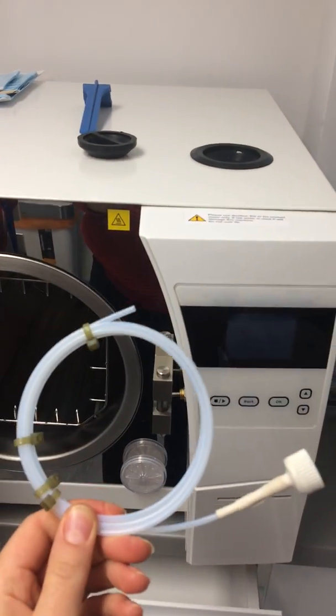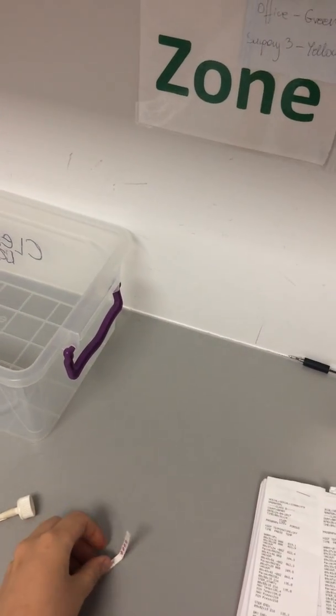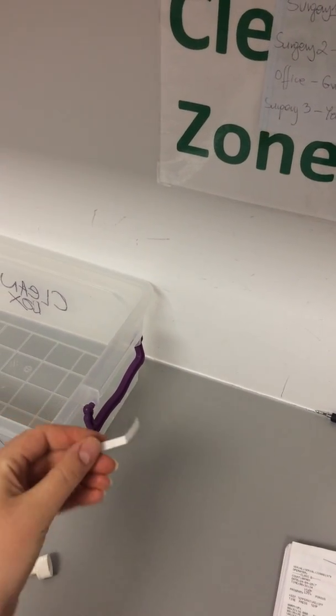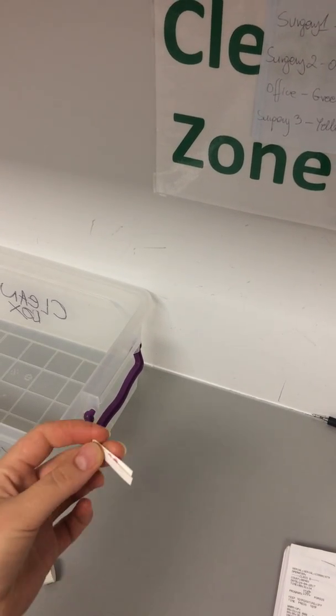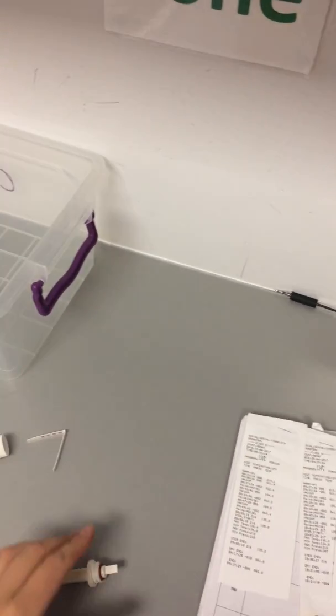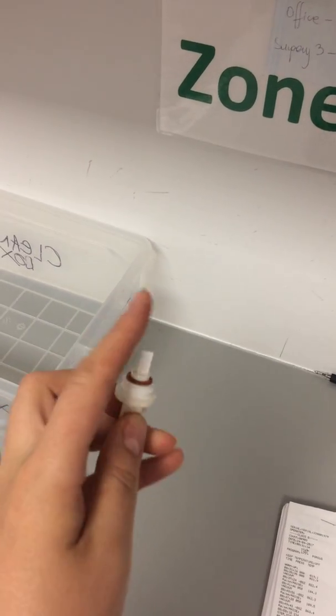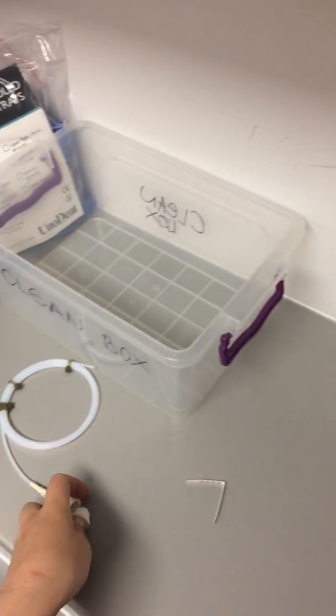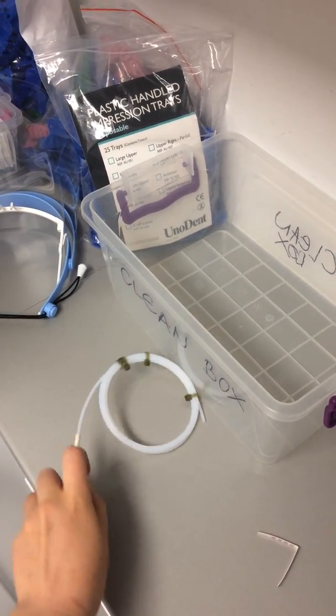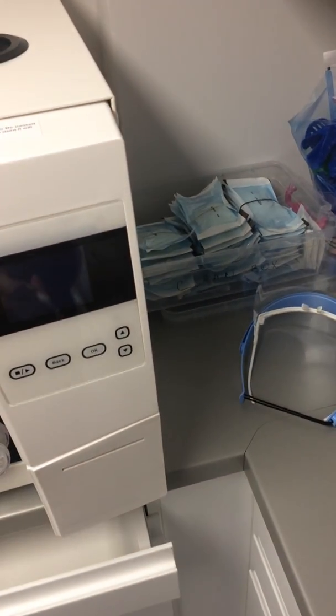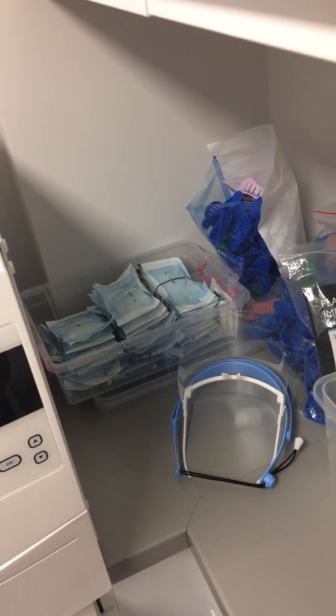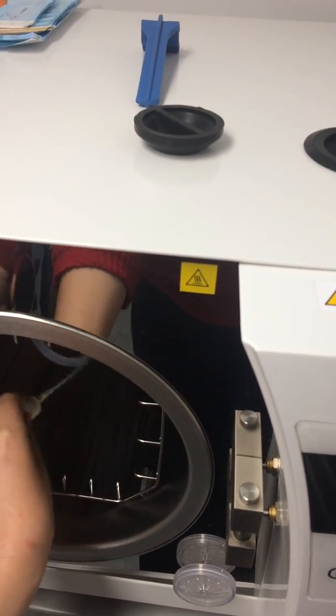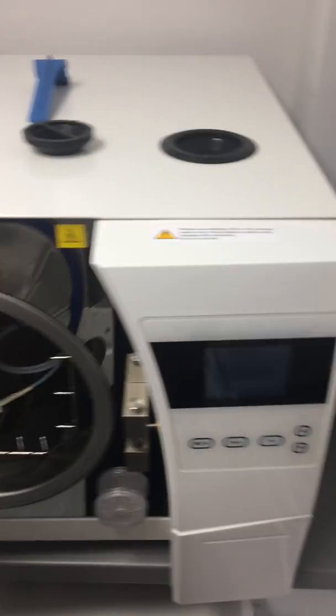We can use a Helix test or a Bowie-Dick test. This is a Helix test. It looks like this. There we insert a test strip. Well, our test strip looks like that. We bend it and we put it this way inside. I already have a ready-made one, you see? So we push it further and close it.